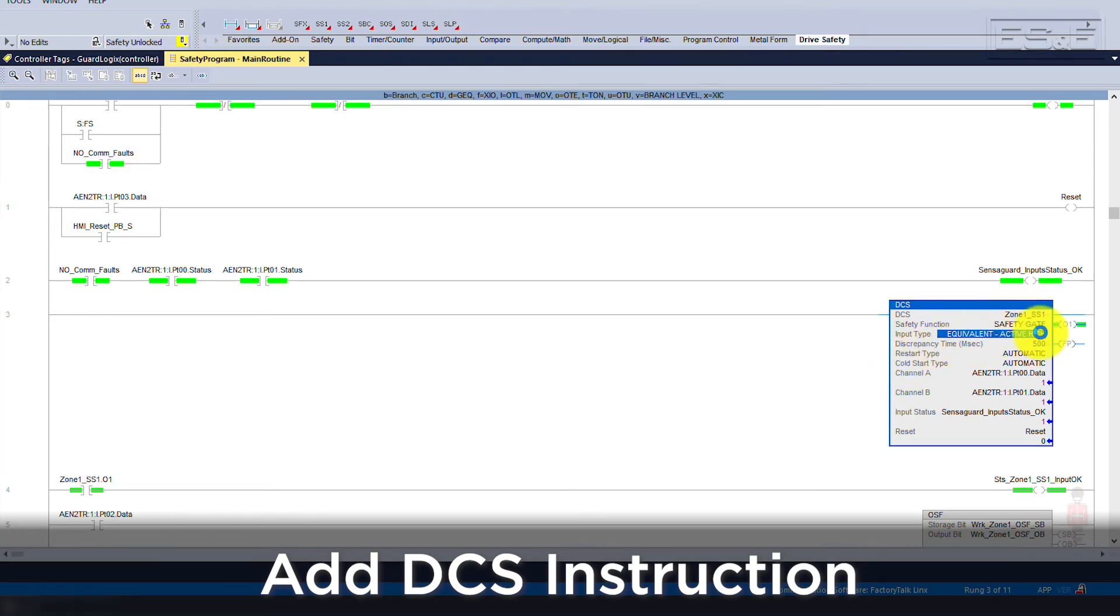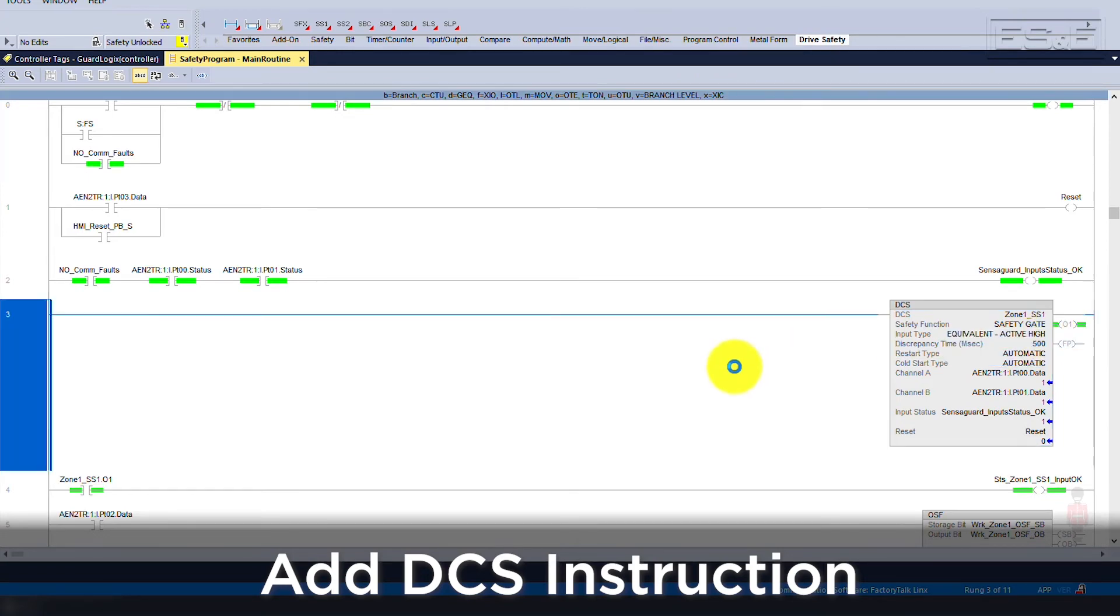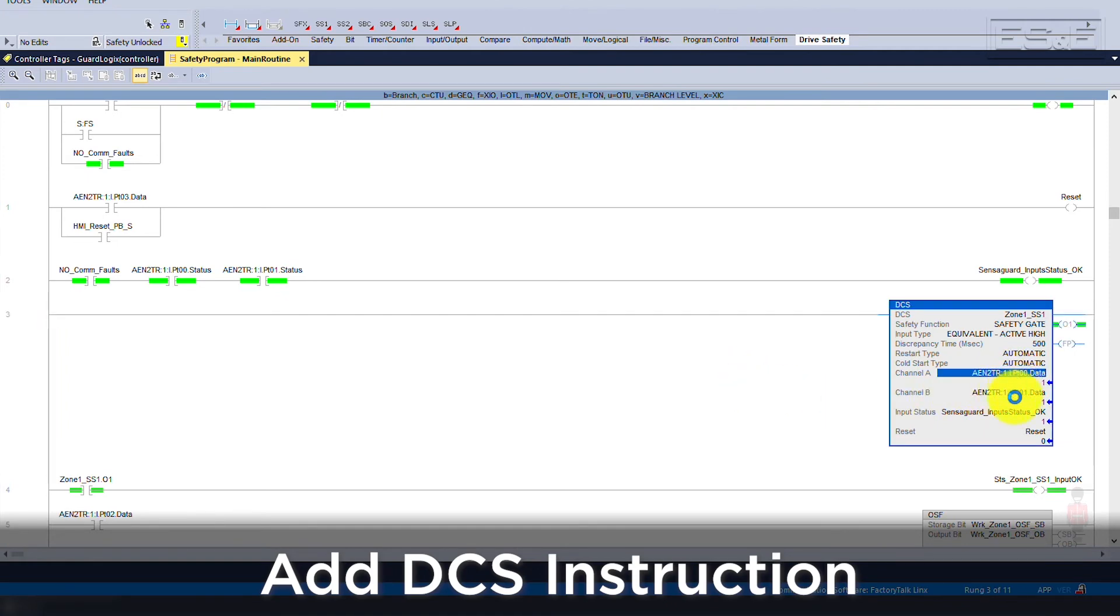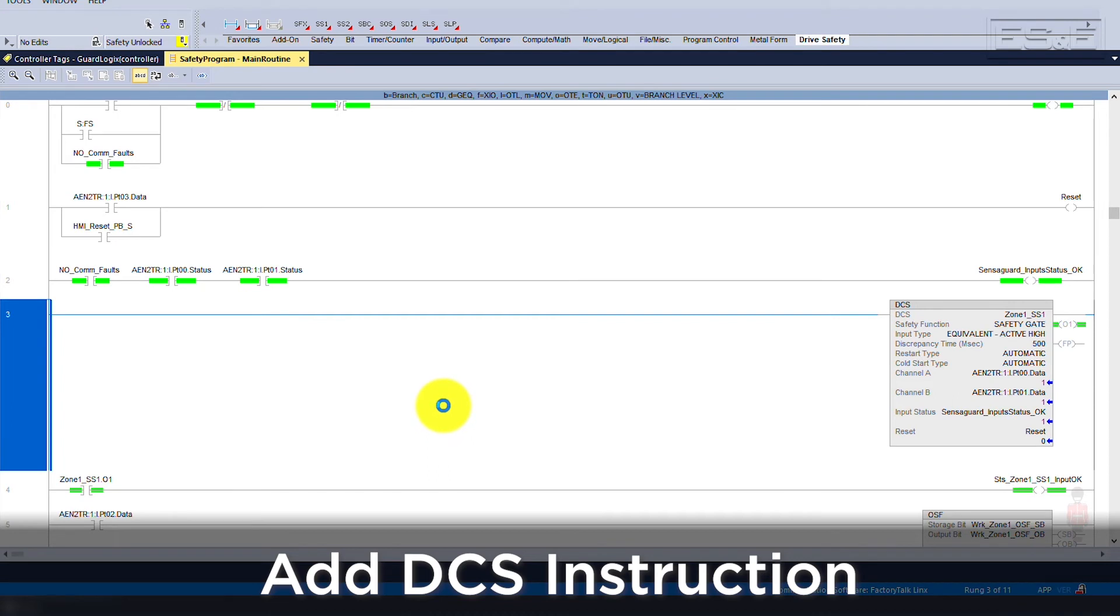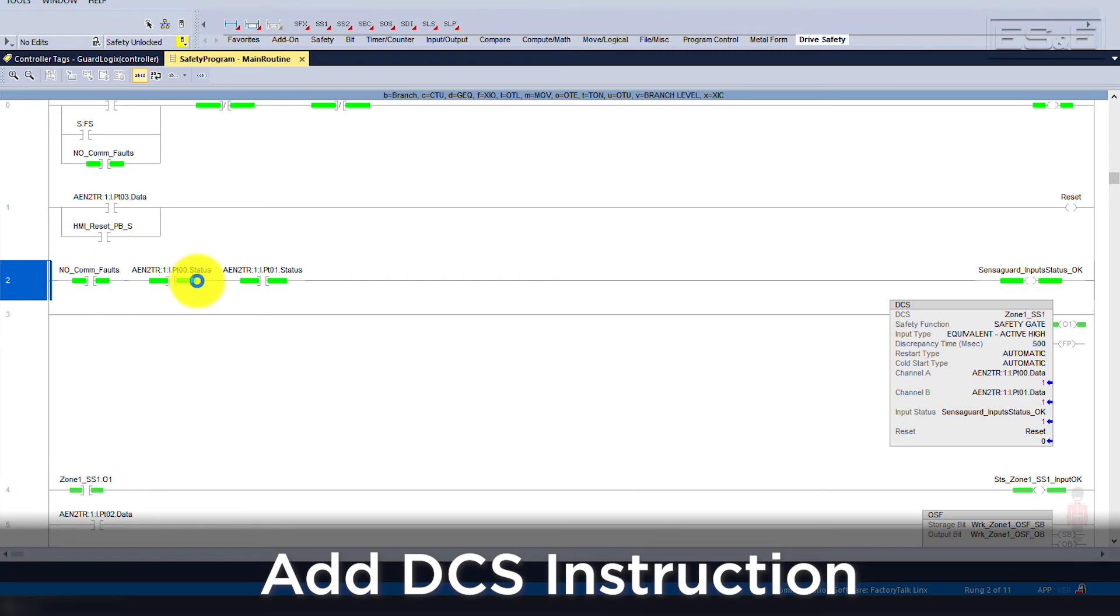For input type, the alternate option would be complementary, meaning the two signals are opposing. Then channel A would be input 0, and channel B would be input 1 for our dual circuits. The input status will be the code that we created on our first rung ensuring that no faults exist for the channels. And last, we will add a reset tag from input 3. Again, the reset does not need to be a safety input, but our example used a safety input for simplicity of the wiring. This reset is not a safety reset, but it is a fault reset in the event that the instruction faults out due to the discrepancy time.